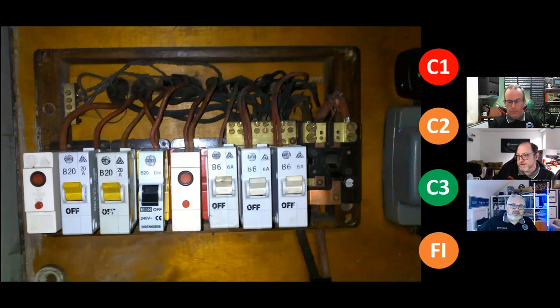How would you go about coding that? Well, is it immediately dangerous? Oh, no. What's the condition of the VIR below the board? That's a thing that I'd want to see. Now, I think most people would, again, I'm going to just dive in here, really. I think C3 is the default. The minute you see VIR, you're just thinking straight away C3. But then when you start looking at it, you think about its condition. Do I touch VIR because it can fall apart? Is it flaking? Your brain works from a C3 FI into a C2 FI.